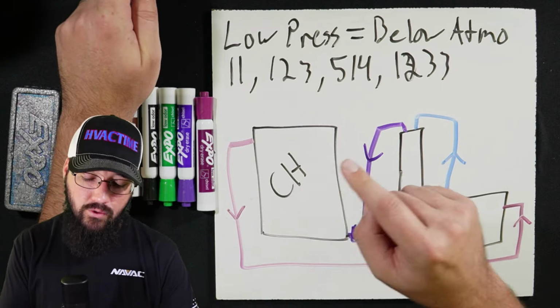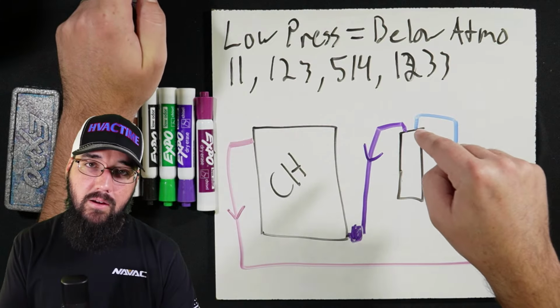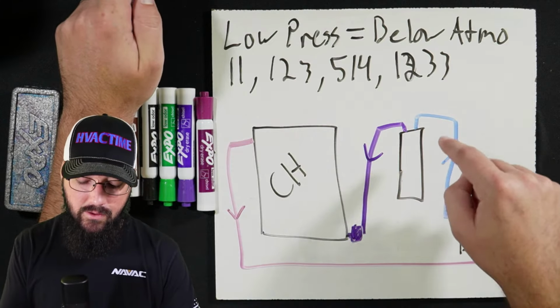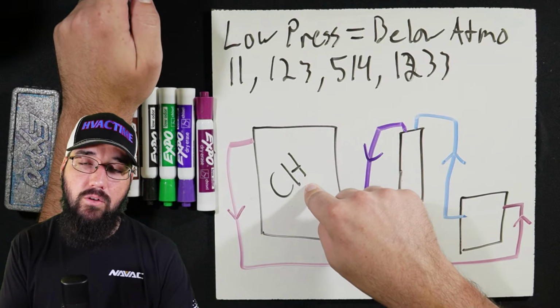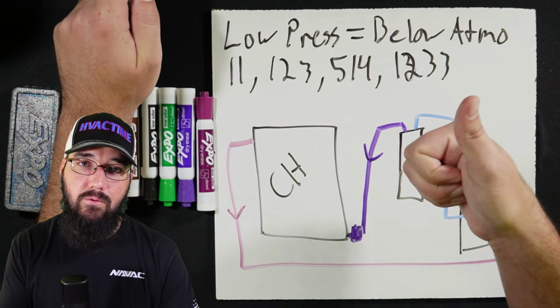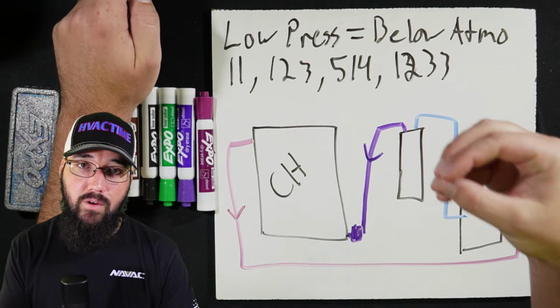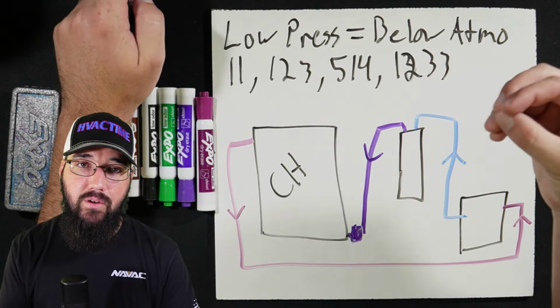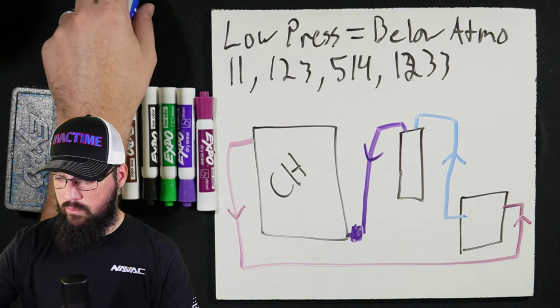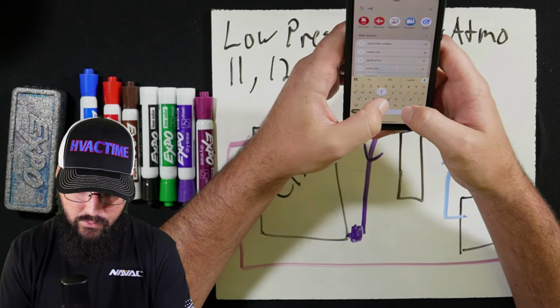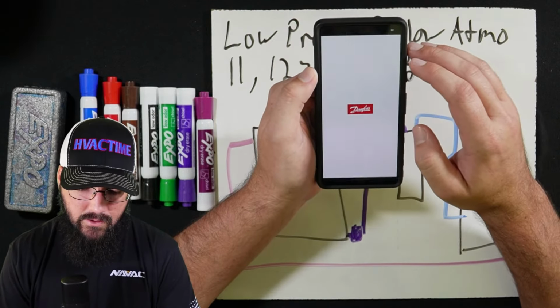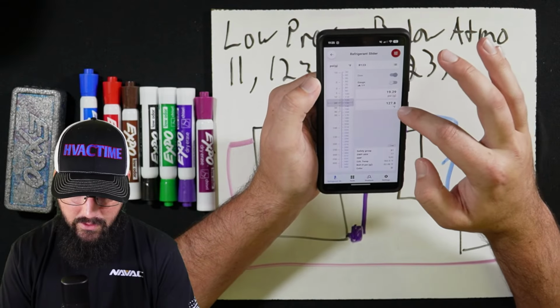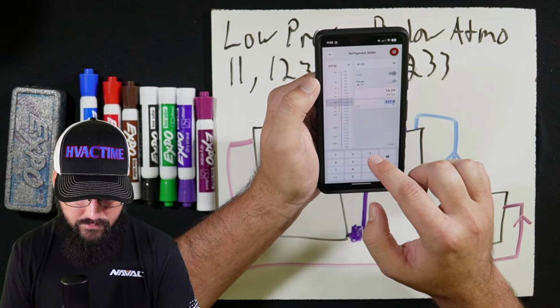All that should be assumed on my part, that you've already done that piece before we're even trying to transfer. So if that be true, before I even hook my hoses up like this, I'm just going to run my vapor line over and pre-charge the chiller with vapor to get us above a freezing saturation. So what pressure does that mean? We could pull up our ref tool. So let's go with a 123 machine. And we want to get above, let's say, 35 degrees of saturation.